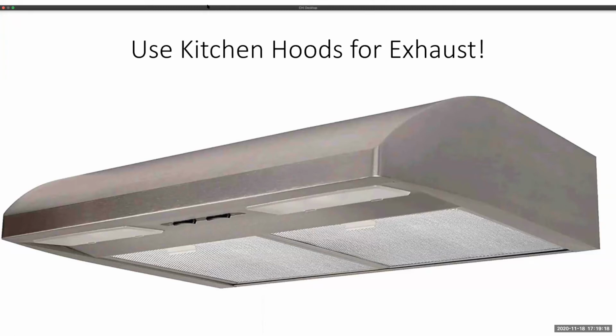But that's also well documented by Lawrence Berkeley National Labs with all sorts of real hood monitoring, where they're watching vapor with different kinds of cameras and sensors. They're basically able to clearly document that you're only getting like 30, 40% capture efficiency on a hood that's at 125 CFM or 100 CFM, which is code minimum where there are codes that require exhaust hoods. Energy Star is 100. You need 250 to do a fantastic job, or at least an 80% capture efficiency, and an ERV is nowhere near close enough to the range or strong enough. And it's just been demonstrated in passive homes that ERVs and HRVs do not effectively exhaust stoves.